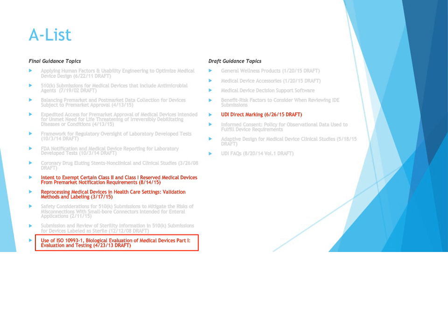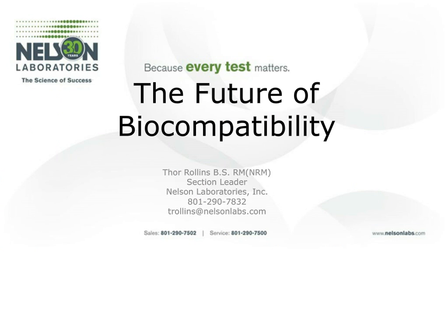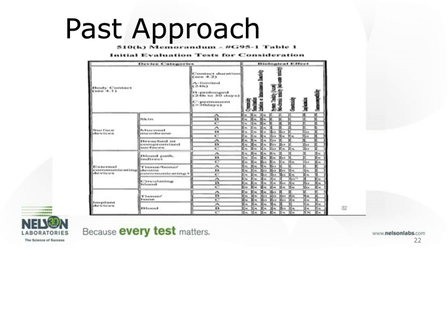So as far as the past approach goes, I think everyone is pretty aware of this chart. For those of you that maybe have never seen this chart before, which I find surprising, I'll explain a little bit. This is in the appendix of ISO 10993-1. Before the latest update of 10993-1, this was actually in the body of the standard. And this has always been kind of the approach that medical device manufacturers take to biocompatibility.